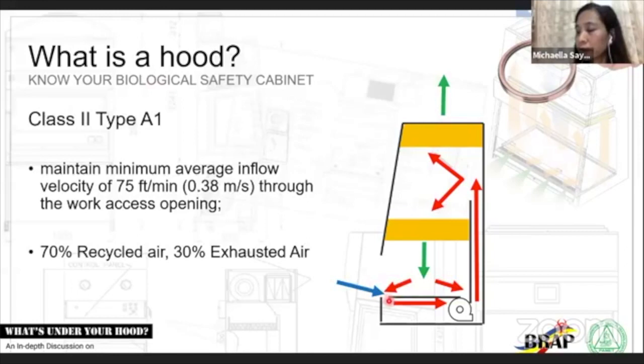Air comes in there, gets pushed by the blower up to the plenum. Some of the air passes out here. Some of the air goes down. So you have your 70-30 ratio of recycled air. So 70% gets recycled here. 30% gets pushed out of the cabinet. So the 70% that gets recycled passes through a HEPA filter, which filters the air, producing clean air that protects your product from contamination.